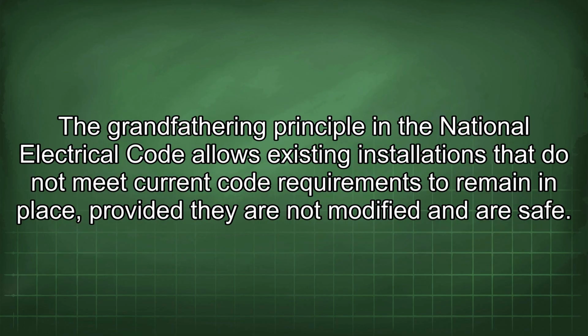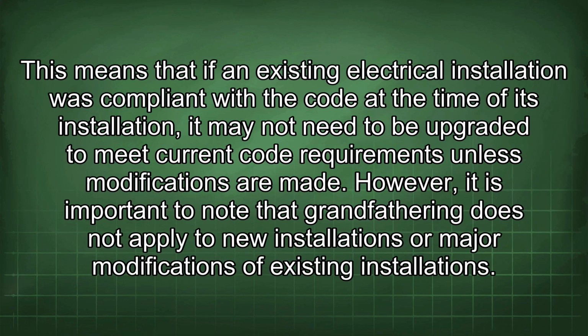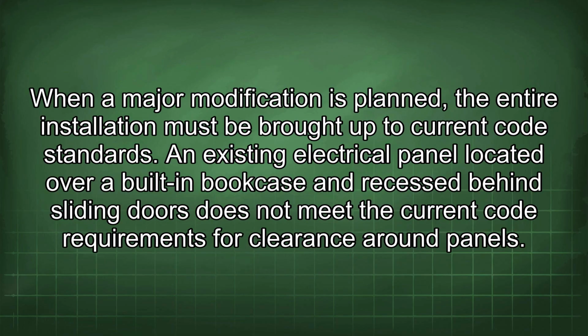The grandfathering principle in the National Electrical Code allows existing installations that do not meet current code requirements to remain in place, provided they are not modified and are safe. This means that if an existing electrical installation was compliant with the code at the time of its installation, it may not need to be upgraded to meet current code requirements unless modifications are made. However, it is important to note that grandfathering does not apply to new installations or major modifications of existing installations. When a major modification is planned, the entire installation must be brought up to current code standards.